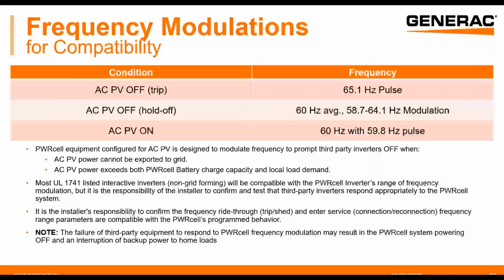If you're in a place where you frequently modify grid connection set points, like installs at the end of the utility line where the installer has adjusted set points so the system connects to the grid, we've definitely seen that with other inverters. Just make sure that if that's the case, they're within our trip threshold range, but it should be pretty standard. I don't think you'll run into a lot of areas where we're not compatible with the inverter installed.